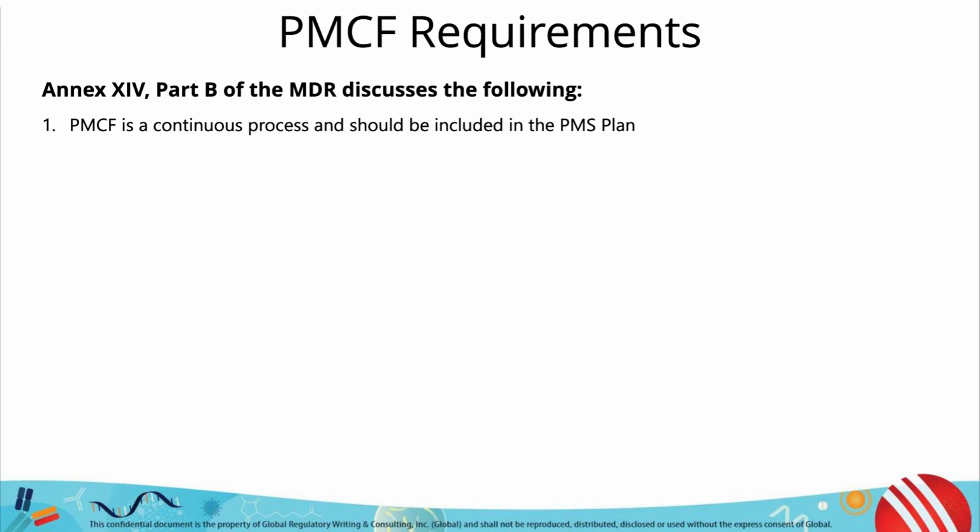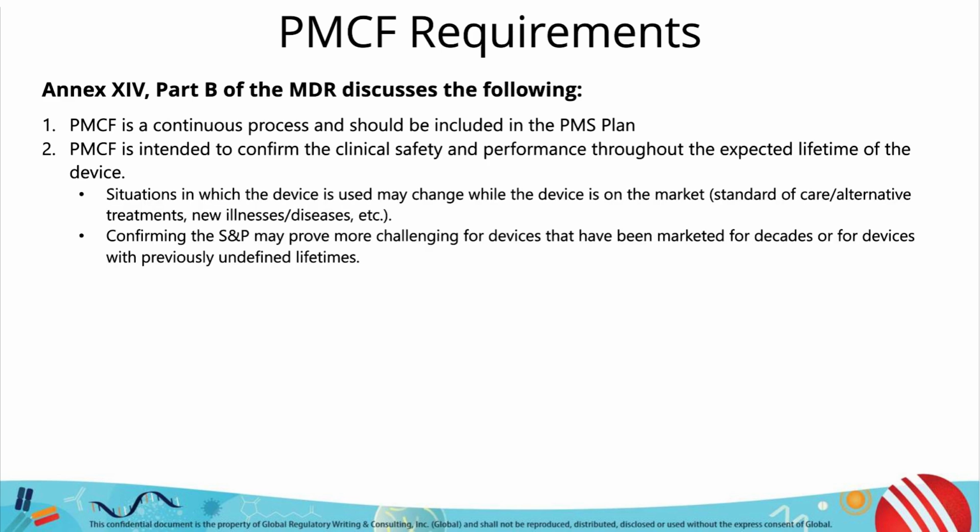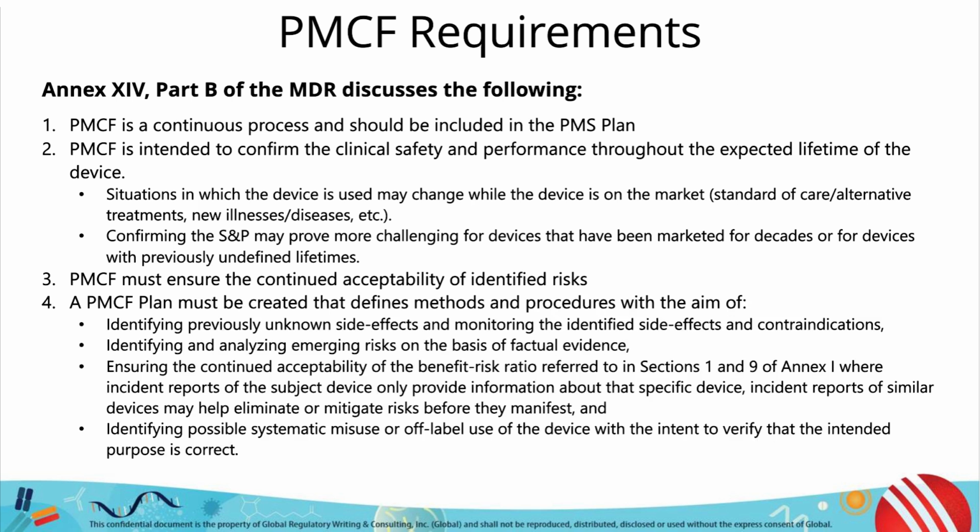The MDR outlines some clear guidance for the PMCF in Annex 14. 1. PMCF is a continuous process that should be included in the PMS plan. 2. PMCF should confirm safety and performance throughout the expected lifetime of the device, with the understanding that there may be changes to the device. 3. PMCF must ensure continued acceptability of identified risks. And 4. The PMCF plan must define methods and procedures of device monitoring.